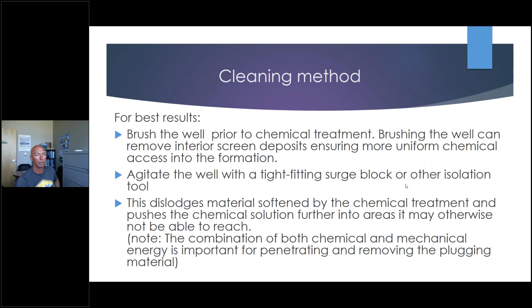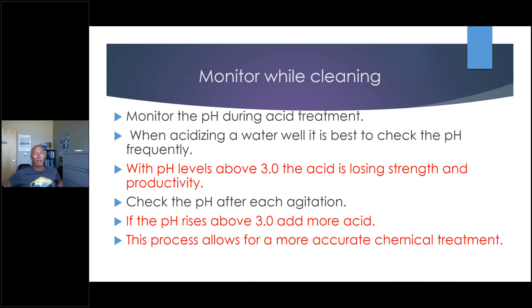We monitor the pH periodically during the process to make sure it stays below 3, because above pH 3 the acid loses its strength and won't do anything to what we're trying to remove. We check the pH after each agitation, and may need to add acid more than once during cleaning — sometimes leaving it overnight and coming back in the morning to do more agitation on the well.